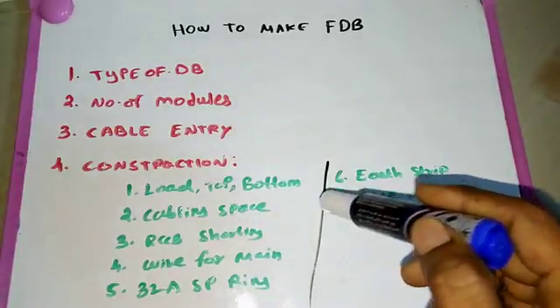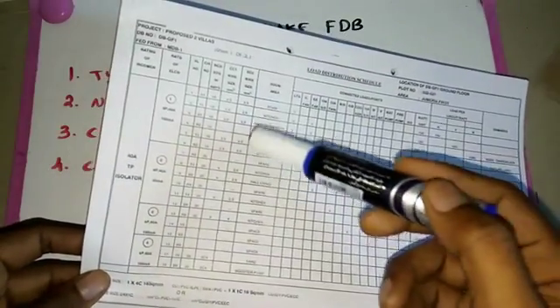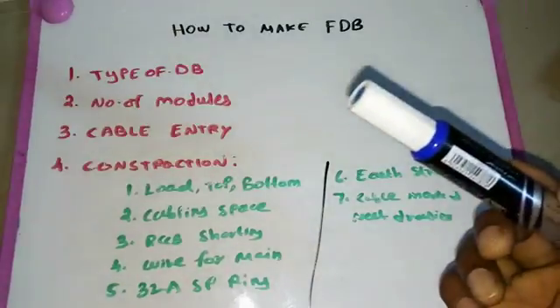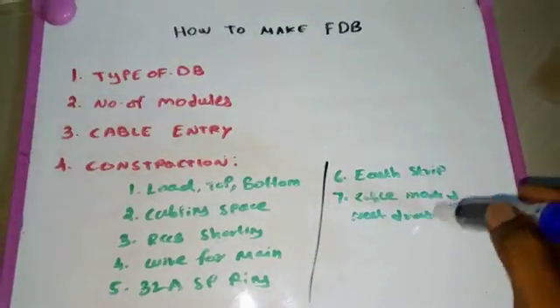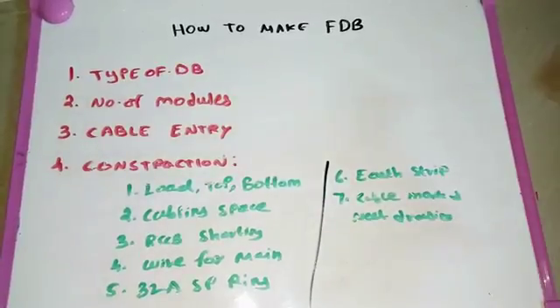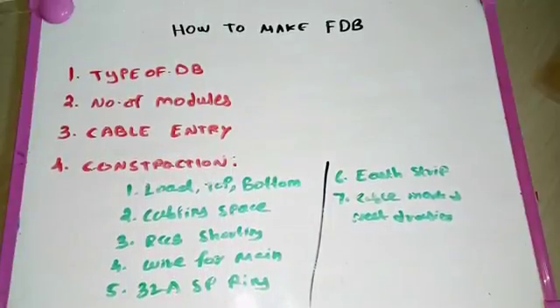The earth strip holes are calculated as the number of circuits plus 5 extra points. For 18 circuits, that is 18 plus 5 equals 23 holes. Finally, we do cable marking and cable dressing to complete the DB. This is a very simple method for making a final distribution board. If you have any doubts, please comment, and don't forget to subscribe.